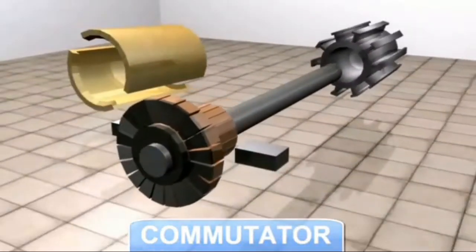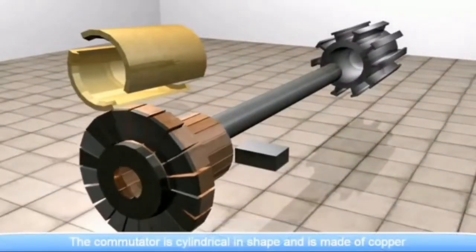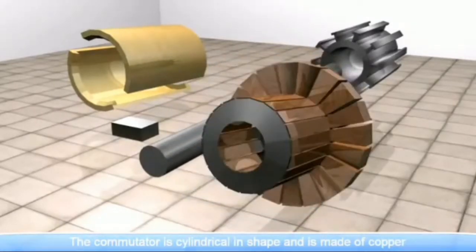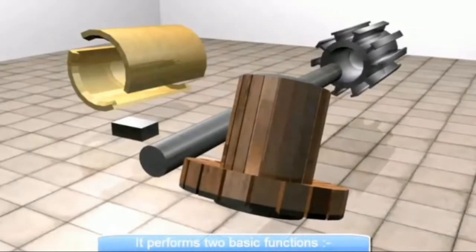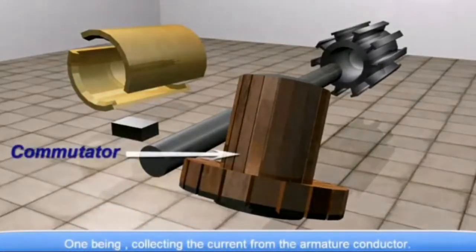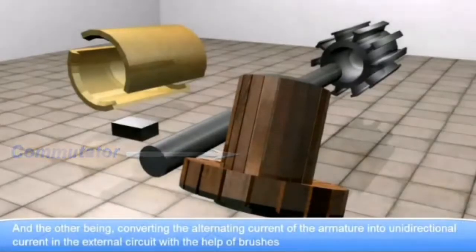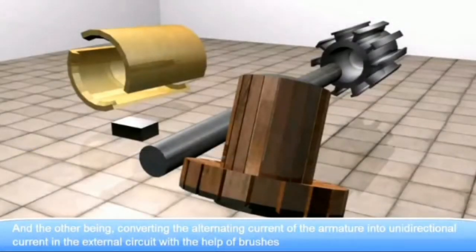The commutator. The commutator is cylindrical in shape and is made up of copper. It performs two basic functions. One being collecting the current from the armature conductor. And the other being converting the alternating current of the armature to unidirectional current in the external circuit with the help of brushes.